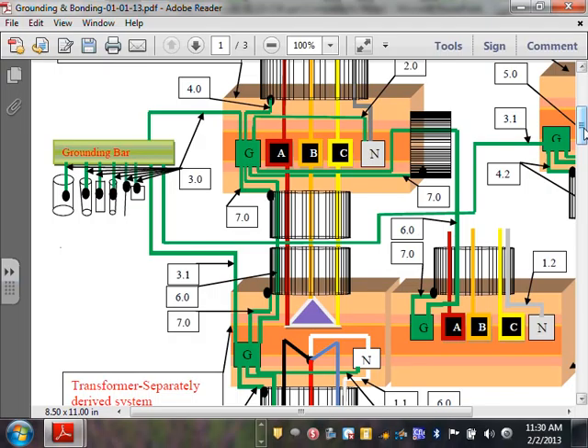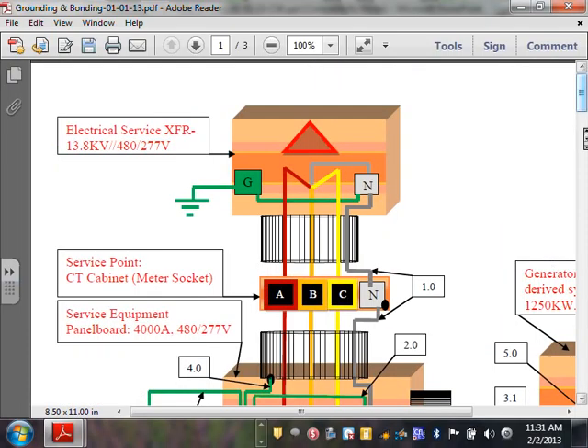And then, thank you, you brought a very good point. So we bonded the flex here from both sides. Then my neutral is bonded to the ground. Then by code, you have to take an equipment grounding conductor. Can you guys see that? A grounding electrode conductor. You take it all the way and you tie it to the ground bar.